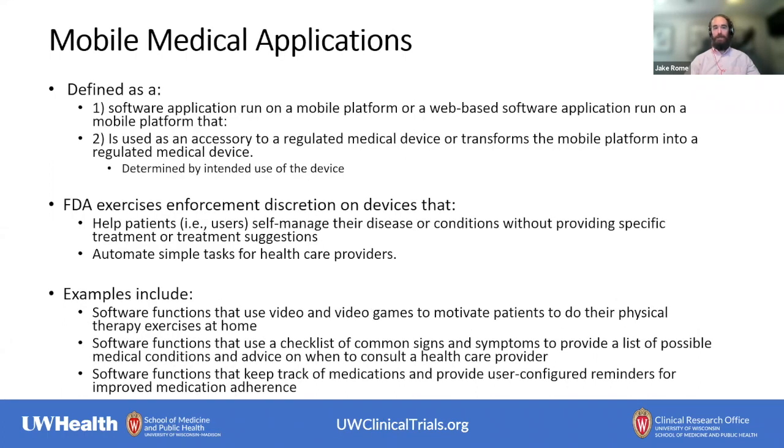But even then, as we talk about SaMD, we talk about devices generally, there are also the mobile medical applications, which are really software that's intended to be its own device, either run on a platform like a smartphone, or potentially taking your smartphone and turning it into its own device. So the FDA in these cases, when you're talking about medical mobile apps, has decided to exercise enforcement discretion based on really what you're doing with the device.